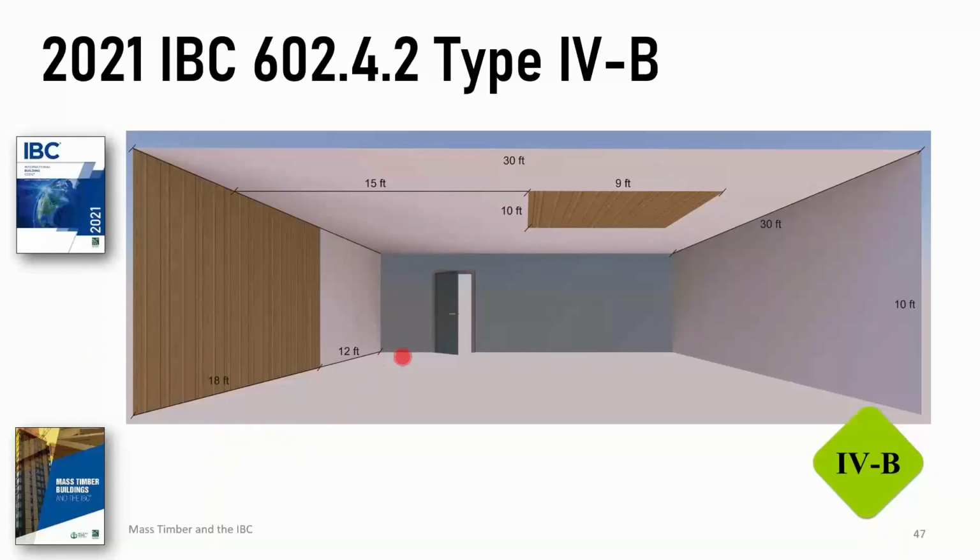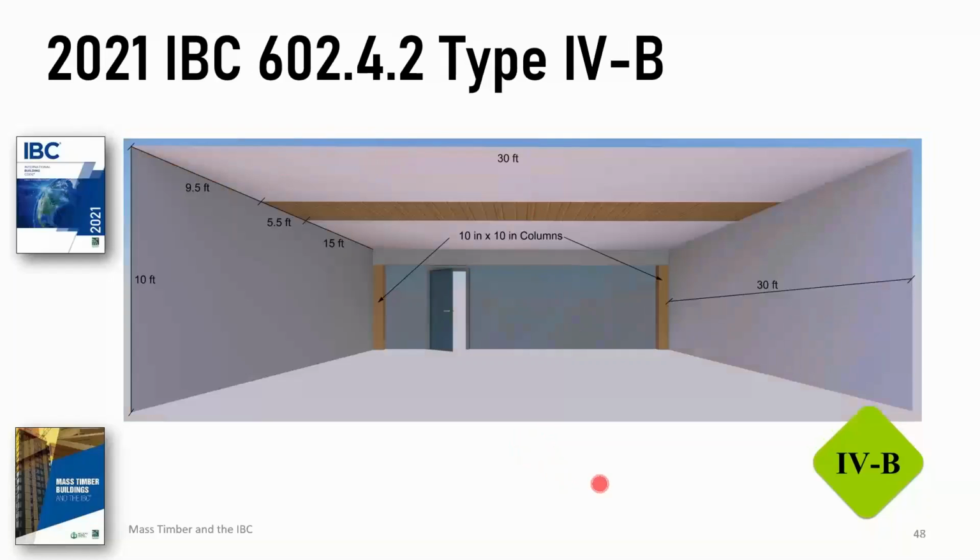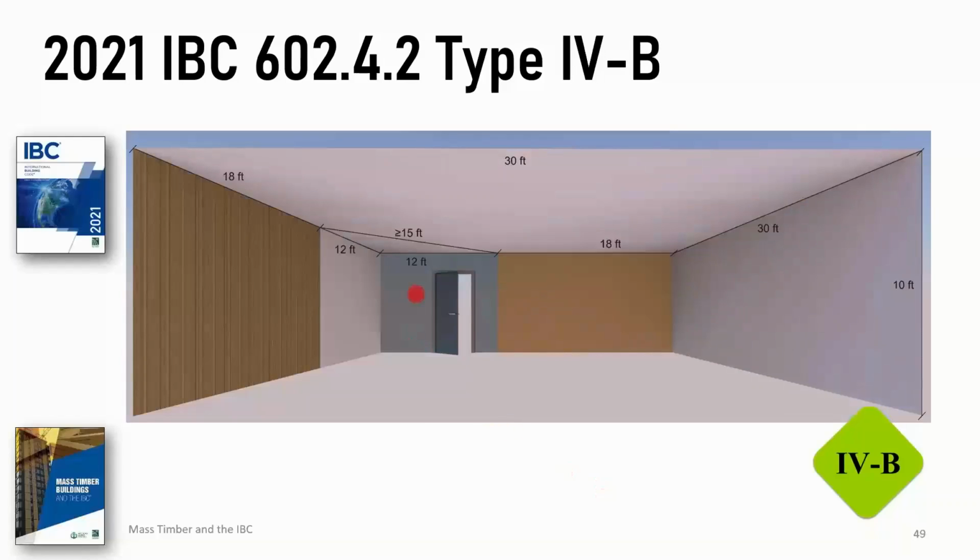It will go out because it doesn't have enough fuel to keep going, and because it is mass timber. But there has to be some separation so they don't reflect off each other. That's the kind of thing they experimented with and tested in the full-scale testing. Okay, this shows 15 feet there. This shows you can measure it as the crow flies between two different wall surfaces.